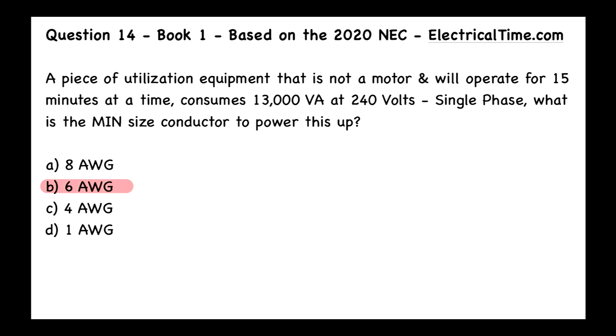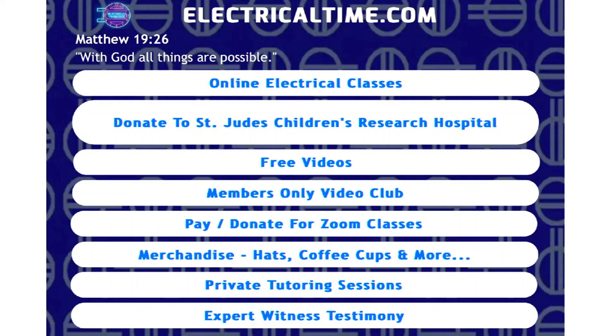When you see VA and volts, you might think Ohm's law or the PIE formula, but let's highlight the important information. We have 13,000 VA at 240 volts single phase. This is not a motor, so we're not dealing with Article 430. The equipment operates for 15 minutes at a time, so this is not considered a continuous load.